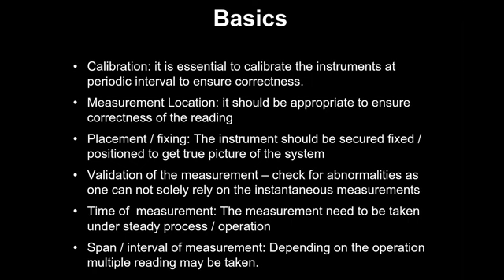Similarly, when we are doing a power measurement for a reactor, if you see a chemical plant reactor, the load keeps on varying. Depending on the content inside, the viscosity and temperature of the material, and the volume, the power drawn by the drive can change. So we have to do the measurement at normal or full operating conditions. Sometimes we do it at two levels, minimum, average and maximum, so that the suggestion can be made accordingly. If voltage optimizers or star delta converters are available, the correct suggestion can be given and they can actually get the saving.